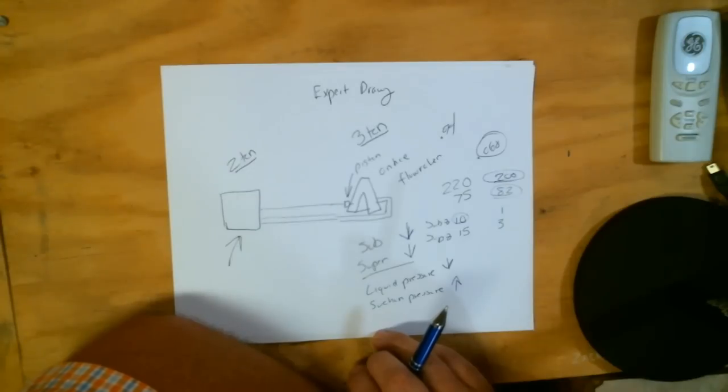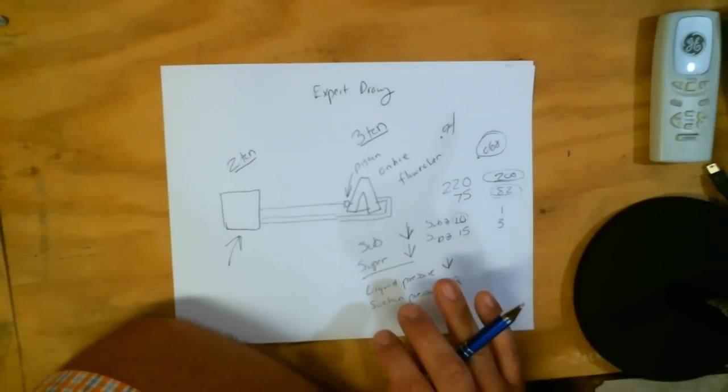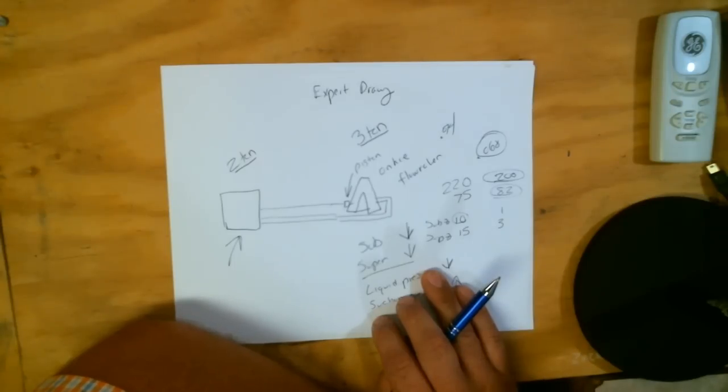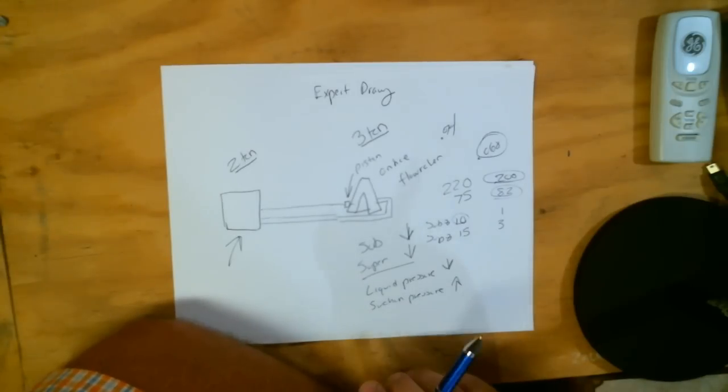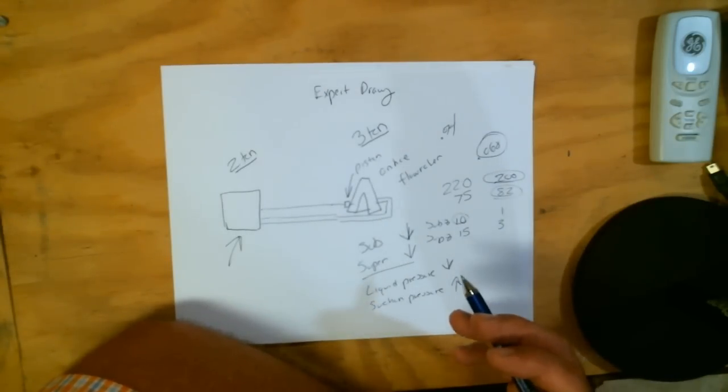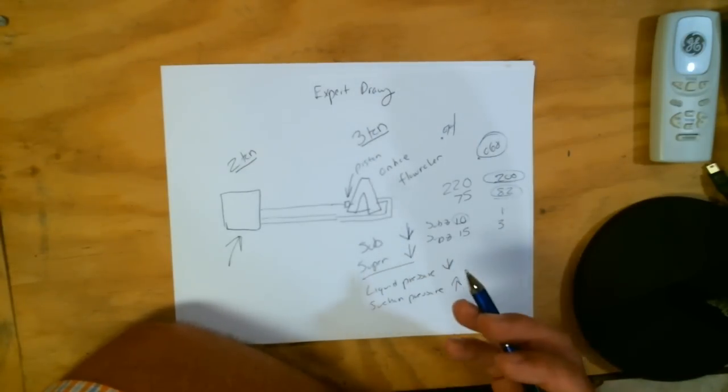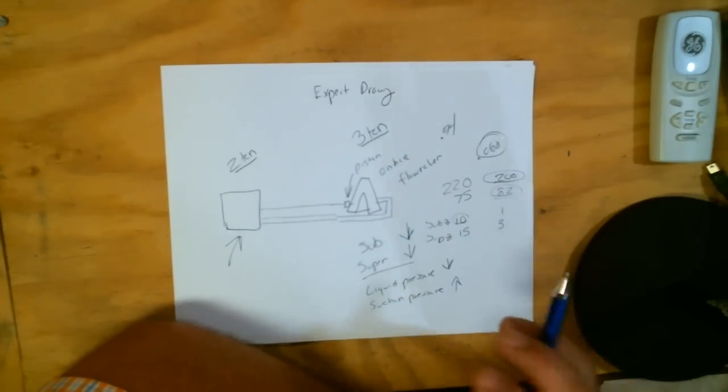Now that's a pretty quick check. You can pump down the system and check that, and like we've said before, we've talked about this a few times. If you're checking a piston and you're going to check it and you're going to be in and out in about 10-15 seconds checking that piston, you don't really have to pull a vacuum either. So it's a really fast process. And the reason why you don't have to pull a vacuum is because it out-gases pretty much for the 20 minutes, 30 minutes afterwards. You can actually see it coming out of the pipe, you'll see those little ripples like you see on a hot day coming off your dash. You'll see that coming out of the pipe.